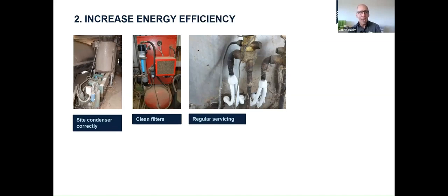It was installed many years ago, and the condenser was near the feed crusher, and the condenser got really mucked up with feed dust. That increased the cooling time on a 12,000 litre vat by 45 minutes each milking. When we cleaned the condenser, it saved 45 minutes of cooling time each milking. That was a huge difference. It just demonstrates the importance of having clean condensers and clean filters.